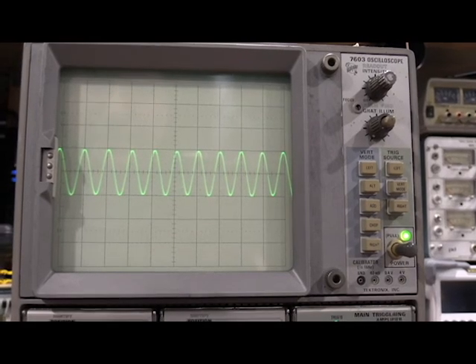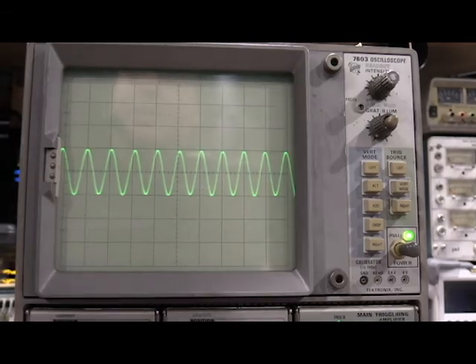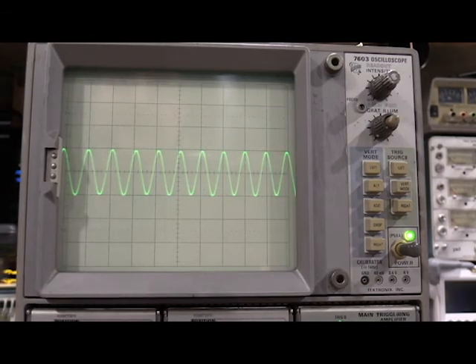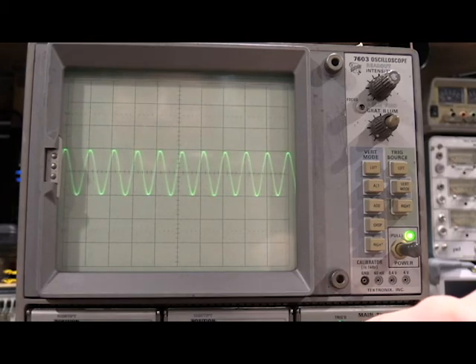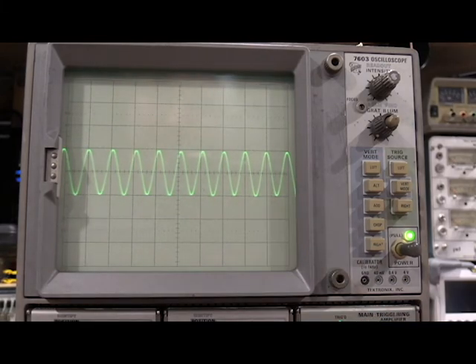Okay, well, as I tried the other way, realized I was actually tuning the wrong capacitor, so I had to go back, set everything back up, get started again. It looks like I have everything kind of in good shape, but in doing this adjustment, I can tell this time base has a horrible sweep linearity problem. So I'm going to need to calibrate that out. That's actually a time base problem, not a frame problem.